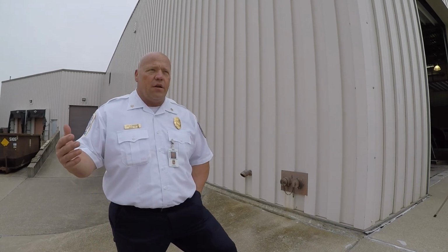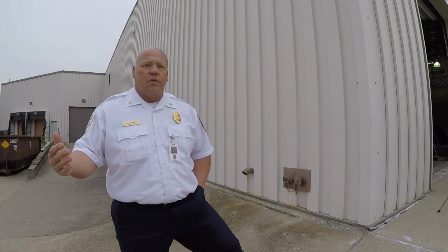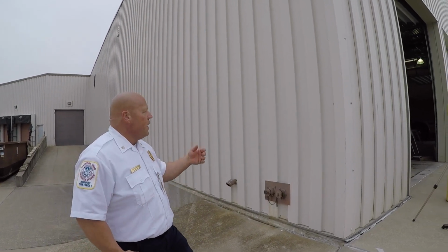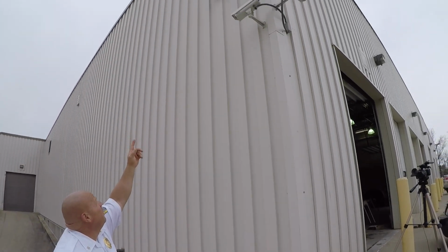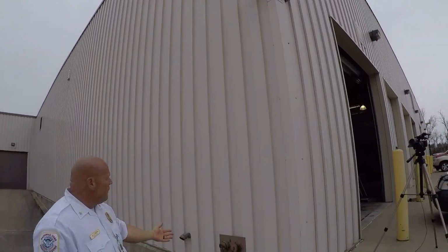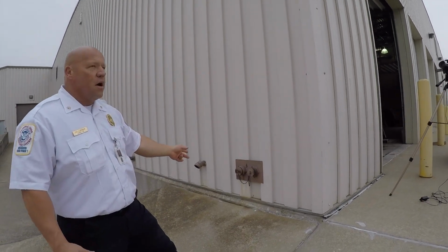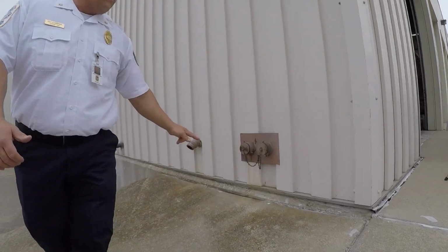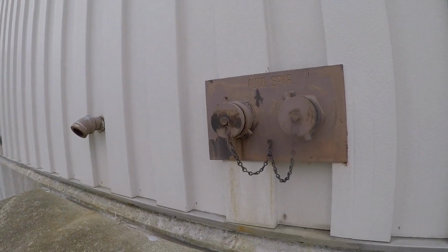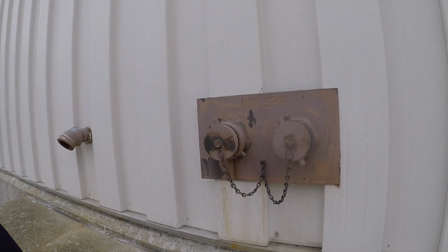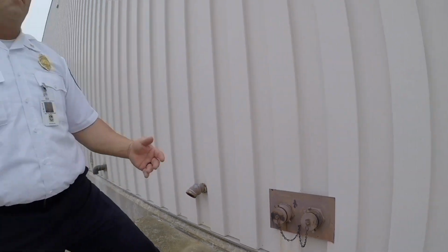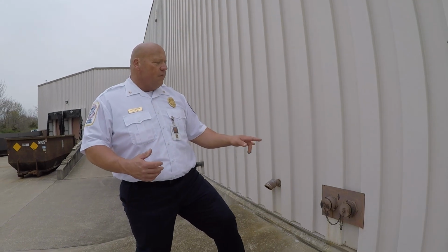So we were dispatched again to a water flow alarm on our 360 on the back corner opposite of where we actually parked. We identified the water gong, which you can see up there. It's actually an electronic bell that was ringing, and we identified the fire department connection for the automatic sprinkler system. So on this one is a Siamese 2.5 connection. Code today requires a 4-inch Storz connection. So you have the opportunity to see both styles of fire department connections.